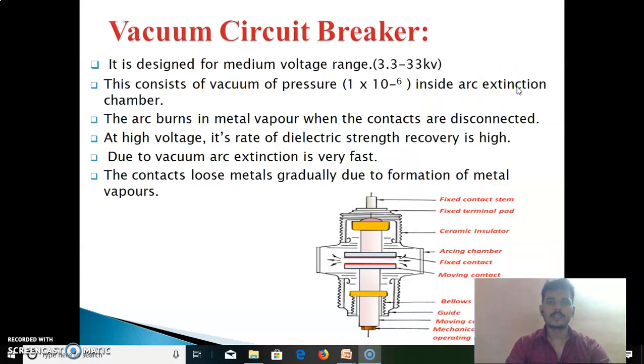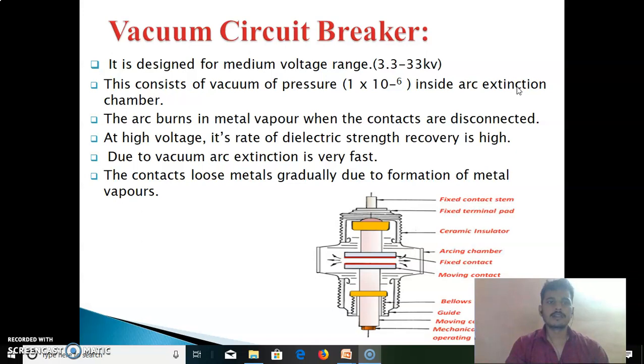Next, we see the vacuum circuit breaker. When the fixed contact and moving contact are placed in vacuum, it is known as a vacuum circuit breaker. It is designed for medium voltage range: 3.3 kV to 33 kV. It consists of vacuum at a pressure of 1×10⁻⁶ inside the arc extinction chamber. The arc burns in metal vapor when the contacts are disconnected. At high voltage, its rate of dielectric strength recovery is high. Due to vacuum, arc extinction is very fast. The contacts lose metal gradually due to formation of metal vapors.